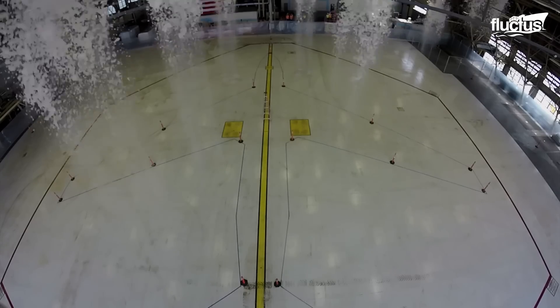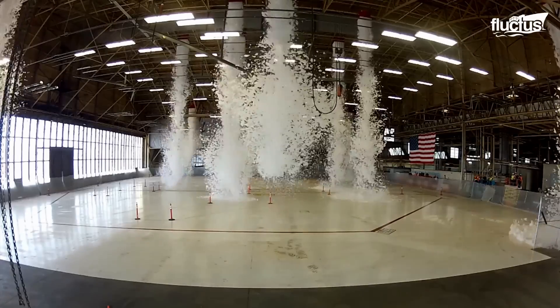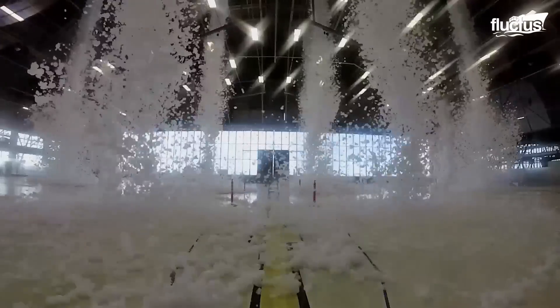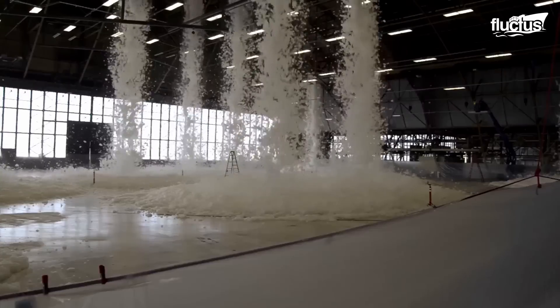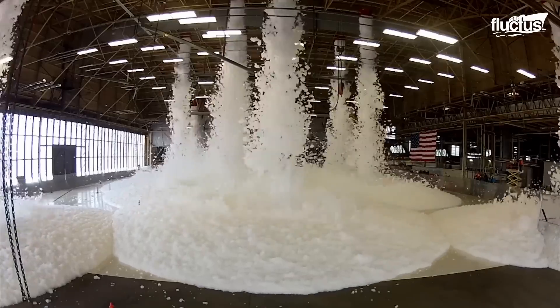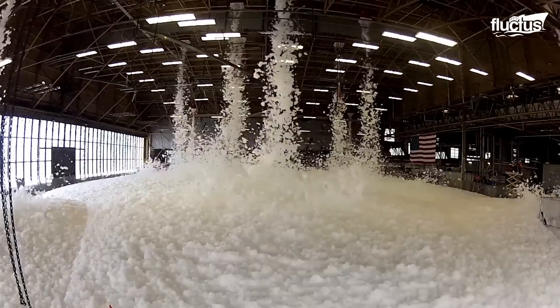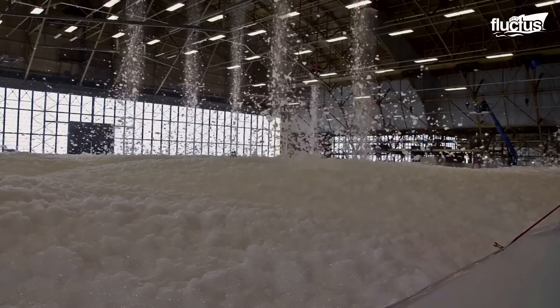For example, a foam testing process for a KC-135 tanker aircraft done by the Air Refueling Wing focused on analyzing the safety and effectiveness of fire suppression systems in their military hangars. Their first objective was to ensure that the foam covered a taped-out silhouette of the KC-135 tanker aircraft within 60 seconds.